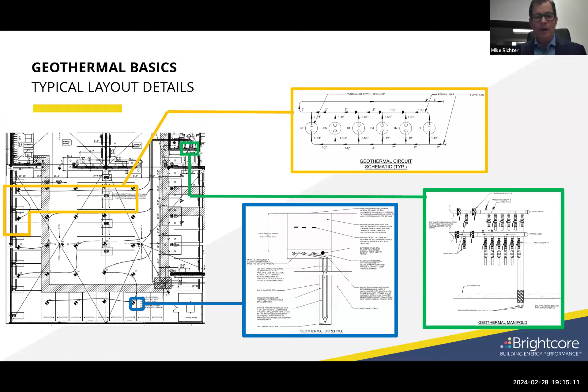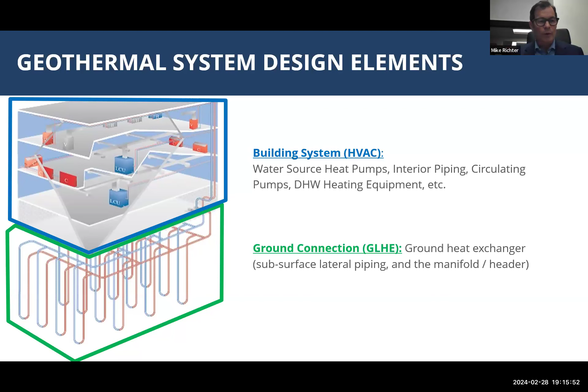I mentioned air source heat pumps is normally what you'd be putting in there. They're effective, they're fantastic, electrically based, but they're not as efficient as ground source. Because why? You're taking the ambient temperature of the air through a heat pump and then getting it to 70 degrees. It could be 10 below zero out there, that's an 80-degree lift. So with ground source, you have that kind of common battery of 55 degrees. That's not going away, and it's particularly efficient.